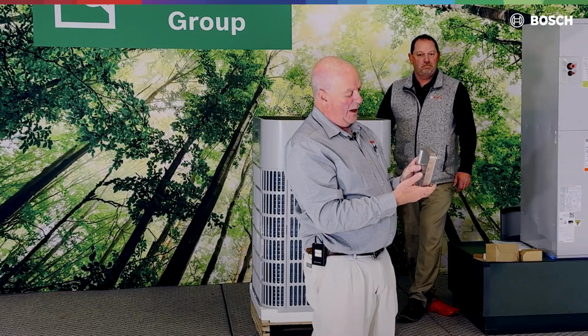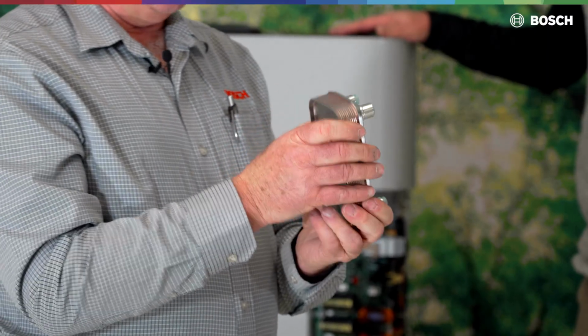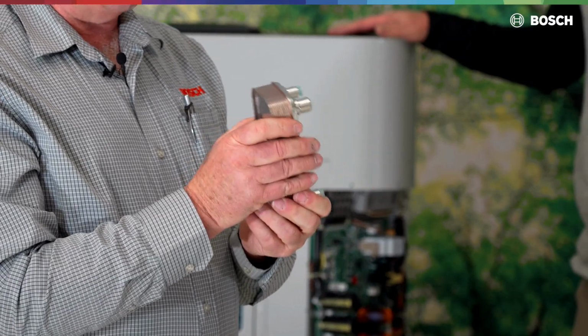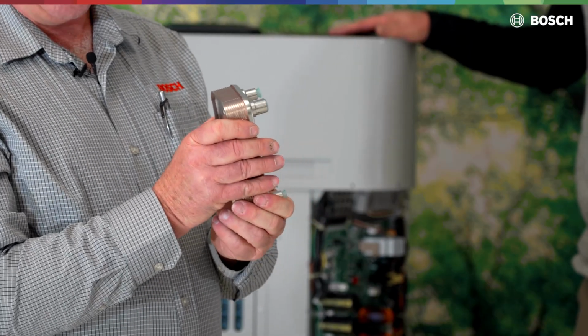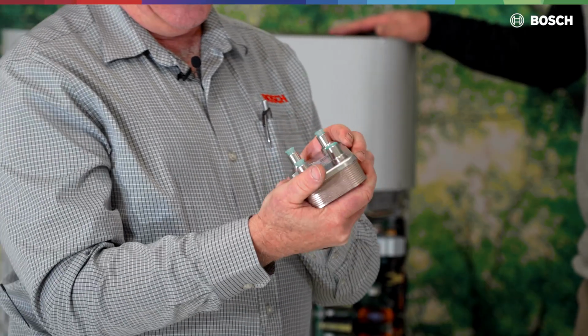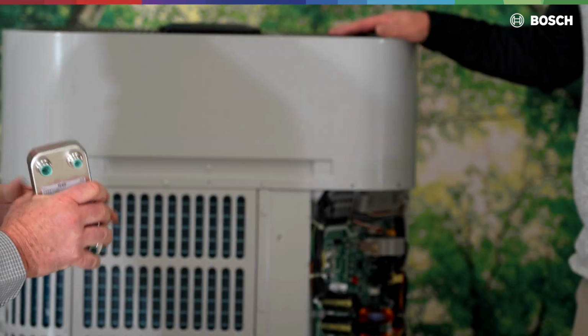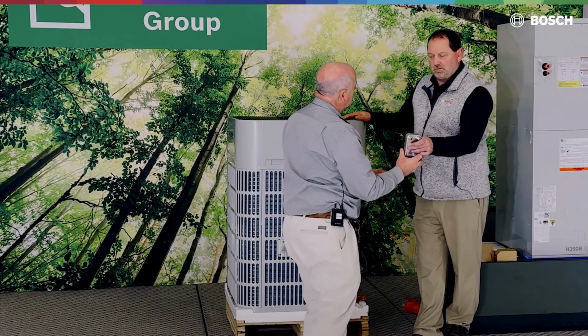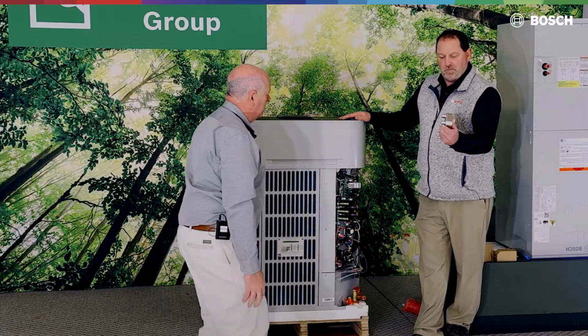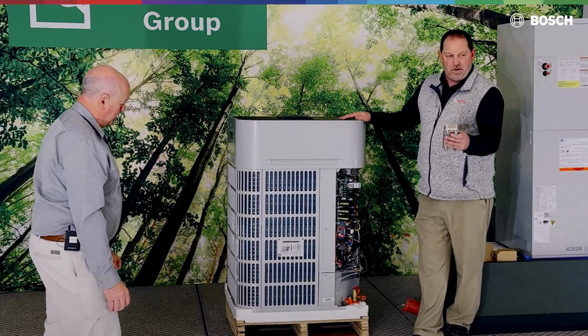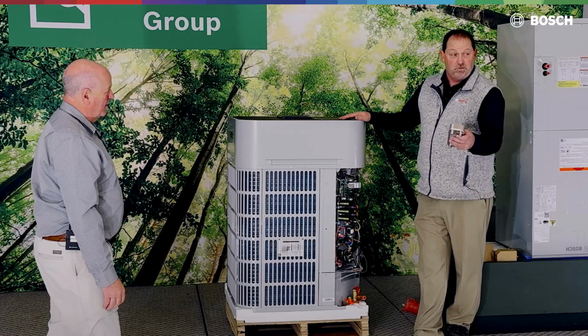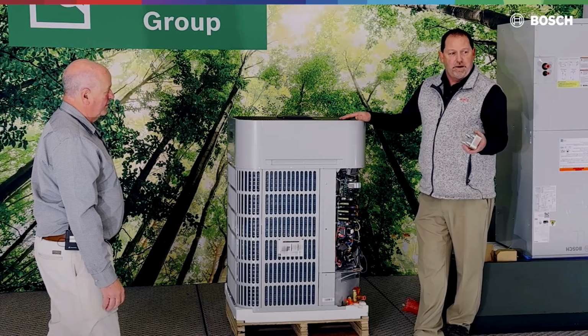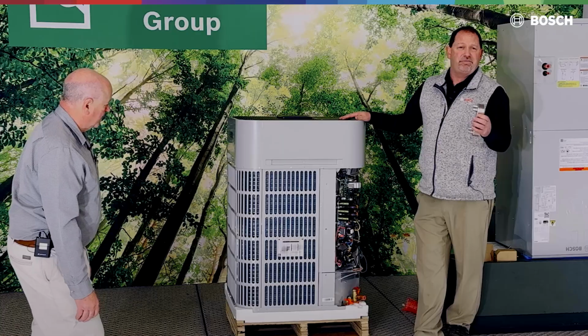In a brazed plate, if you take a look, there are individual plates, and on one side of the plate is refrigerant from this side, and on the other side of the plate is refrigerant from this side. So we offer the opportunity to either cool or heat a product without intermixing the gases or the refrigerant. And this is the key important component of the Ultra to make it successful. And Chris, at what temperature does it actually start moving refrigerant through? Well, not only did I mention we added an EEVC, which is an additional electronic expansion valve, we also added an extra solenoid. This solenoid activates at 50 degrees.